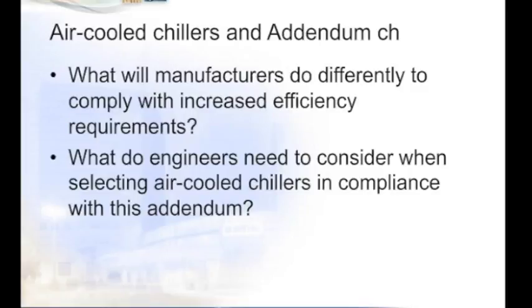Thanks, Pat. That was a lot of numbers. Now I want to discuss a couple items, talk about manufacturers and engineers and how selection of air-cooled chillers will be affected with this adopted addendum. Manufacturers will have to consider the new requirements and how to comply with the requirements, which will be adopted by a number of states. Many manufacturers currently offer air and water-cooled chillers, which are able to comply with parts of the new efficiency requirements. However, some manufacturers only comply when they're using their higher efficiency or highest efficiency chillers. When they are able to comply, they're typically only complying in part load conditions. So in general, these chillers will probably have a higher first cost, but many locations have utility rebates available, and of course owners will see long-term operating costs that will help hold the total project cost down.